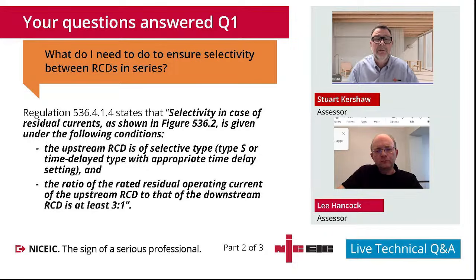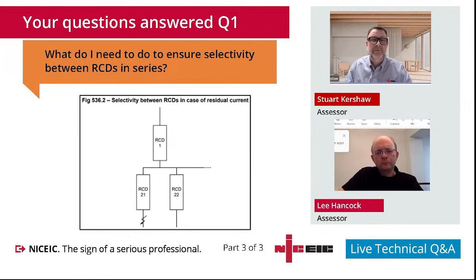Hence why manufacturers usually make them at 300 milliamps, 100 milliamps, and 30 milliamps, but also the time delay nature for upstream RCDs. Again, it's imperative that we follow manufacturer's instructions on the settings for these S-type devices, because obviously we've got other regulations to consider. 314, division of installation, minimising inconvenience in the event of a fault, if we have an upstream RCD disconnect at the same time as the downstream, or sometimes, as is often the case, before the RCD we want to disconnect.